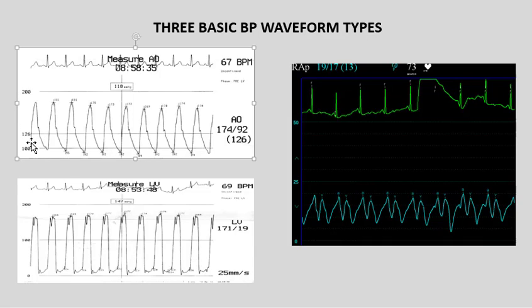Notice the scale. This is 200 and 100, so 0 is down here. So the arterial trace operates along the upper part of the curve of the ventricle, whereas the ventricle drops down to near 0. The baseline is 0. Top value is around 200. Can be greater, of course, but most of our charts measure on scales of 0 to 200 to record arterial pressures. These two aren't difficult.